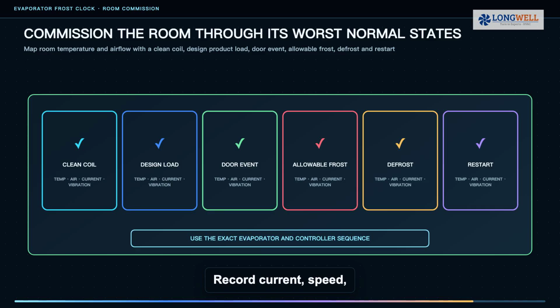Record current, speed, vibration and sound while confirming product zone uniformity.